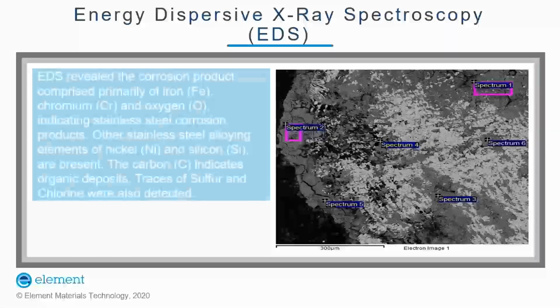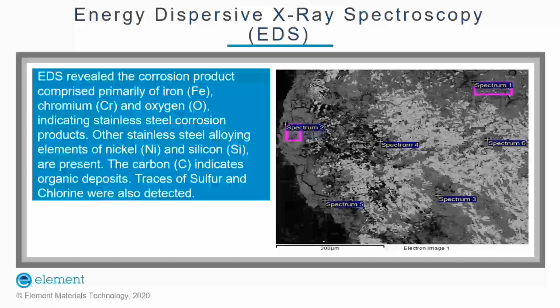EDS analysis, also known as energy dispersive X-ray spectroscopy, was used to determine the elemental contents of the corrosion product. EDS analysis of the weld area revealed the corrosion product to be comprised primarily of iron, chromium, and oxygen, indicating stainless steel corrosion products. Other stainless steel alloying elements of nickel and silicon were also detected. The carbon indicates organic deposits. Traces of sulfur and chlorine were also detected.